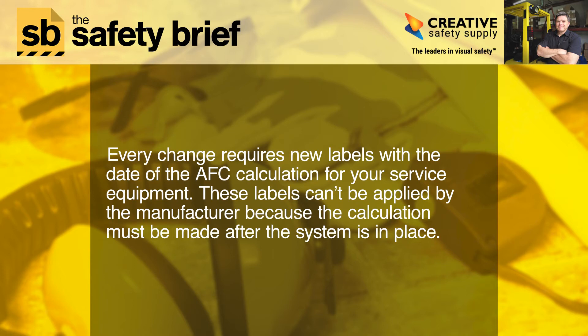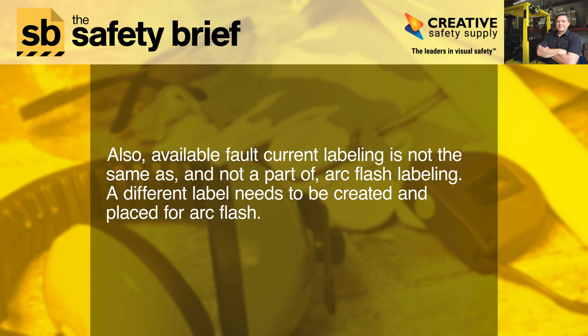Every change requires new labels with the date of the AFC calculation for your service equipment. These labels can't be applied by the manufacturer because the calculation must be made after the system is in place. Also, available fault current labeling is not the same as, and not a part of, arc flash labeling. A different label needs to be created and placed for arc flash.